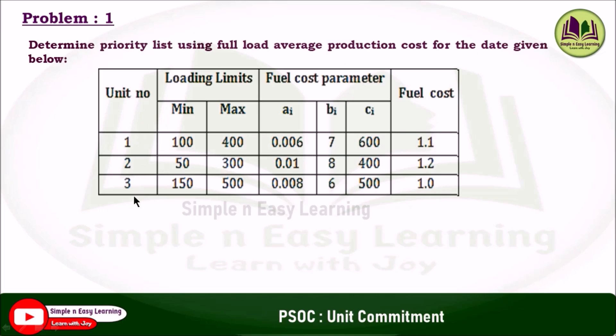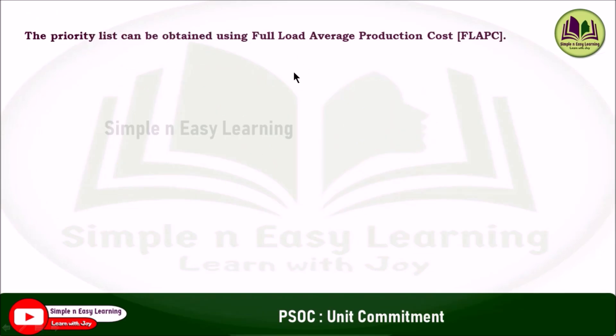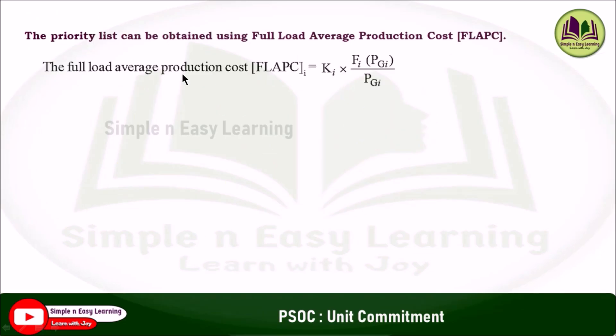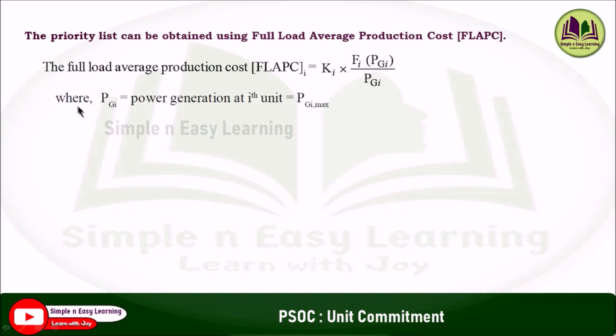In this table, units 1, 2, and 3 are given with their loading limits — minimum and maximum — along with fuel cost parameters AI, BI, and CI. The fuel costs are given as 1.1, 1.2, and 1. The priority list can be obtained using full load average production cost. The FLAPC formula is: FLAPC_i = K_i × F_i(PG_i) / PG_i, where PG_i is the power generation of the ith unit equal to PG_i max.